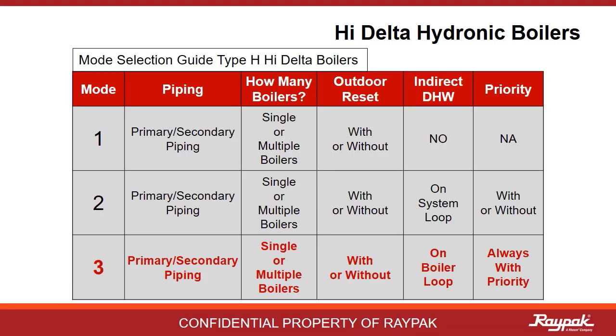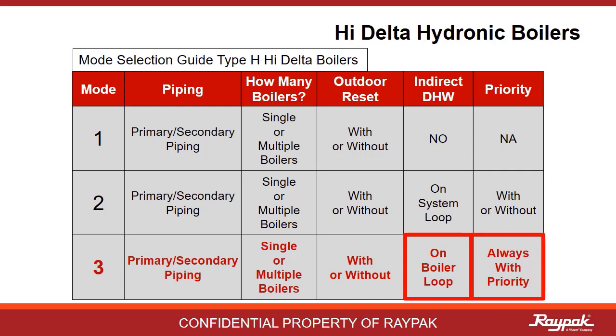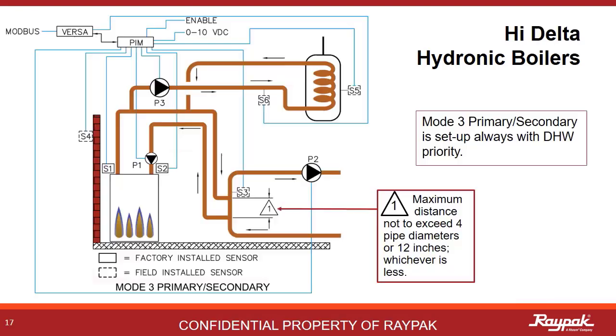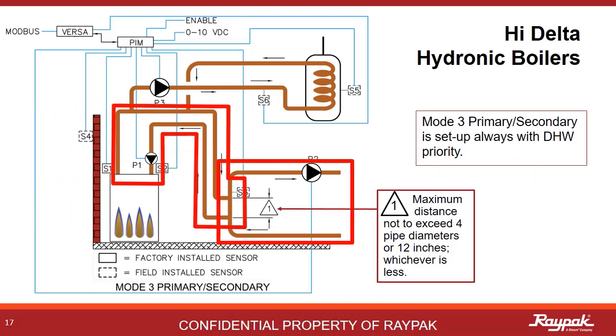Now moving on to the Mode 3 discussion. In Mode 3, the indirect domestic hot water is on the boiler loop. Mode 3 systems are always run with priority. This is a Mode 3 primary-secondary single boiler system. You have a boiler loop and a system loop, and the indirect domestic hot water heat exchanger is on the boiler loop in this case.